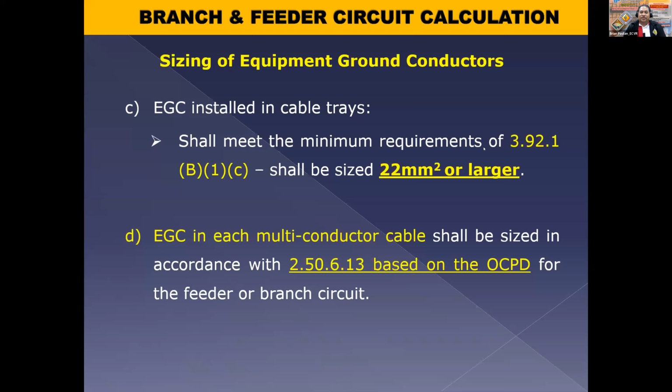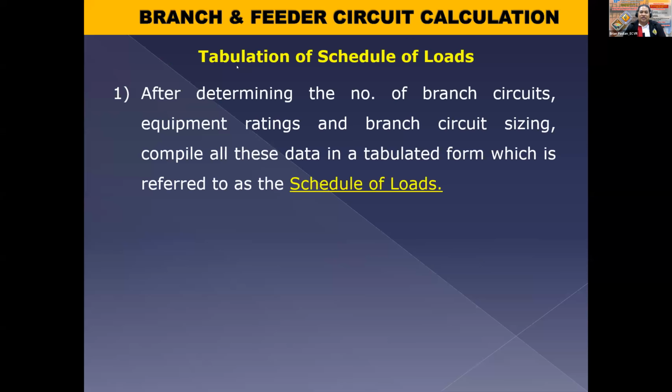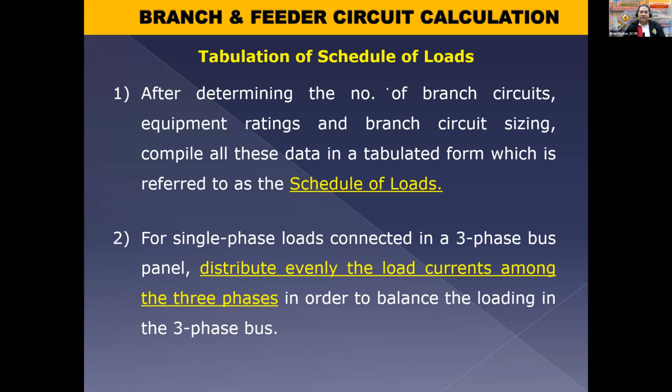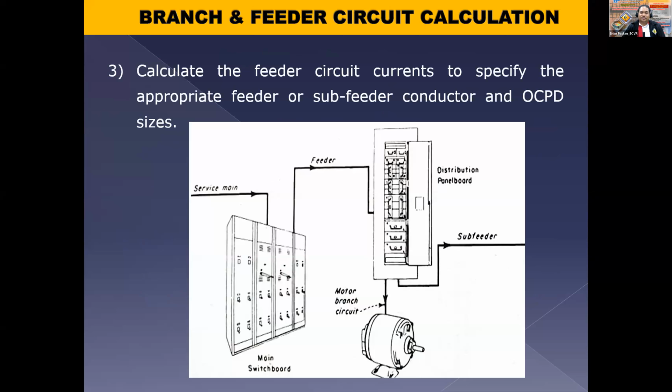Okay, so tapos na tayo sa lahat ng conductors. Now, the next step is tabulation na of schedule of loads. Okay? So, ito na next step natin is para to compute na the feeder conductor sizes. Tapos na tayo sa branch circuit, no? So, tabulate everything in the load schedule. Now, for single phase loads na in a three-phase bus, dapat i-balance natin yung distribution ng currents, no? Among the three phases, no? Para mag-balance loading tayo. Okay?